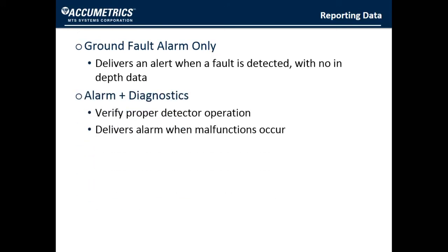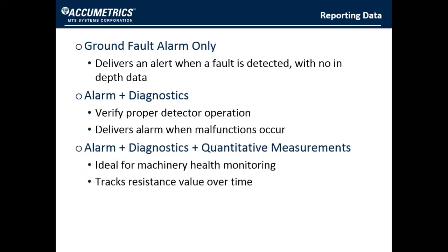Adding diagnostics that verify the proper ground detector operation or provide an alarm when the unit malfunctions gives the operator further confidence that he is really protected. And finally, having additional information like quantitative measurements for health or condition monitoring gives the operator a lot more insight to make the appropriate decision. These are the kinds of interfaces that are much better than just a simple ground fault alarm, and all of these are available with Accumetrics Earth Fault Resistance Monitor.